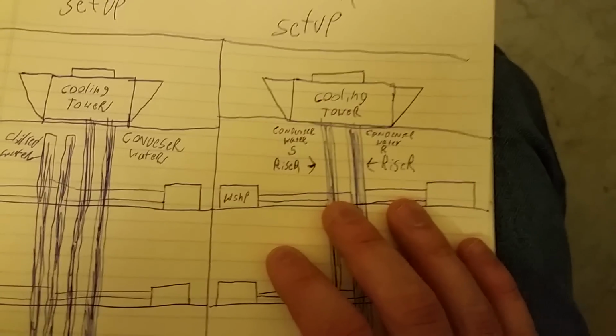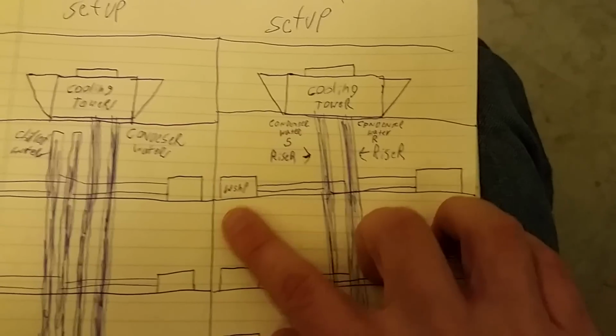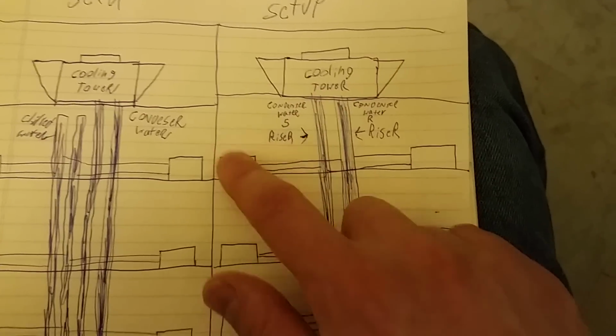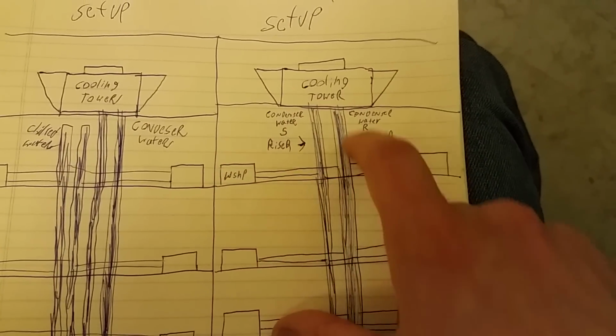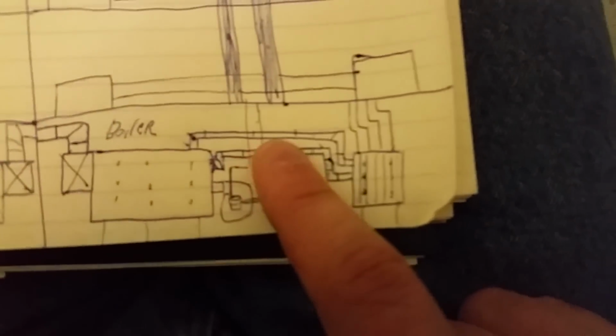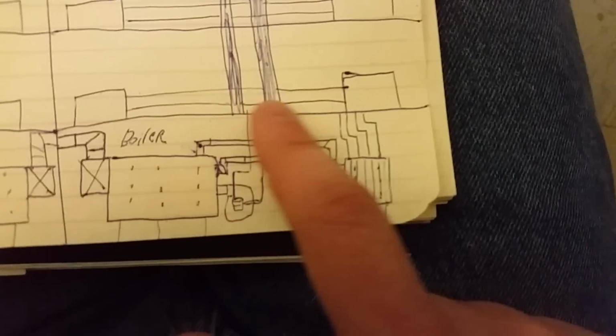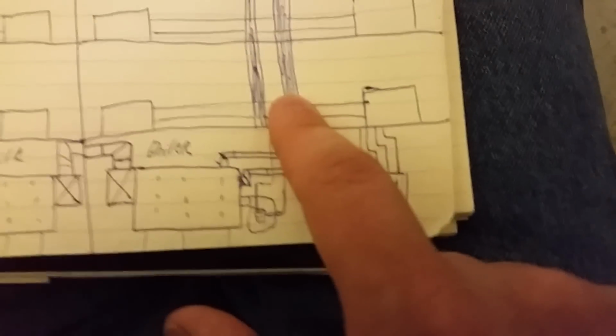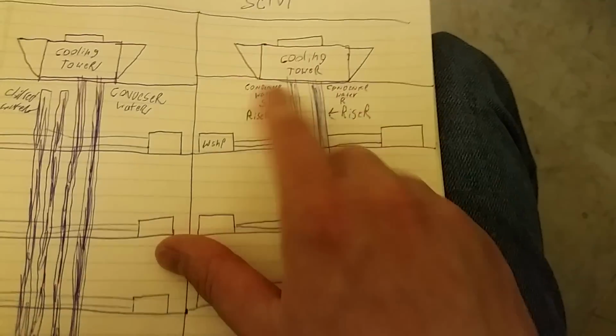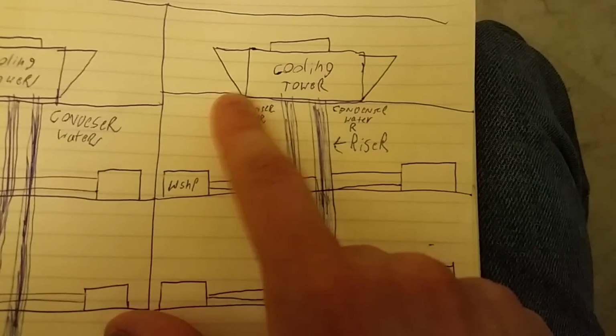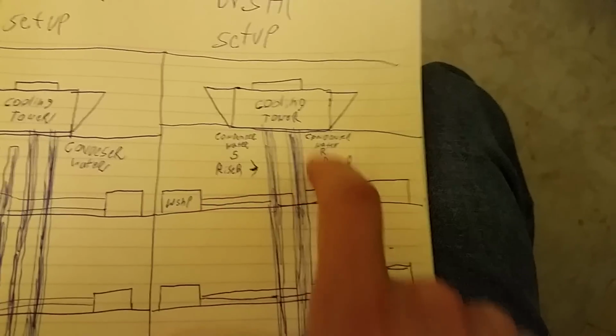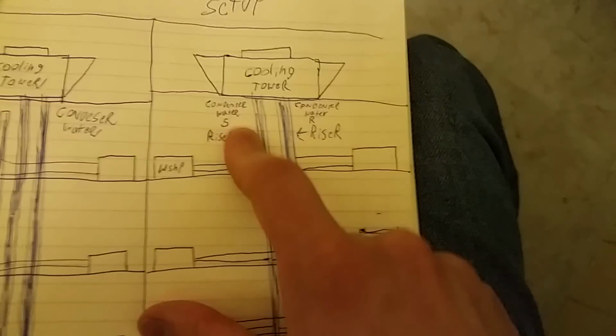So again, this is very simple. You have water source heat pumps, cooled by the supply water, your condenser water, which then goes back to the tower to be recooled and recirculate through the building. Now in winter with heating, you have a boiler down here, and this is a heat exchanger. The condenser water loop comes through the heat exchanger and circulates through the building. Obviously, your tower is now bypassed. The tower's cut off. You drain the tower. Now it becomes a closed loop system.